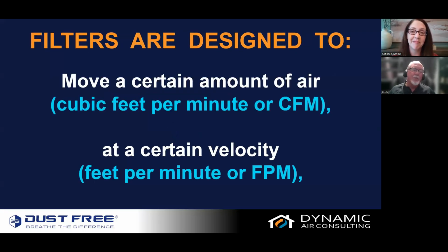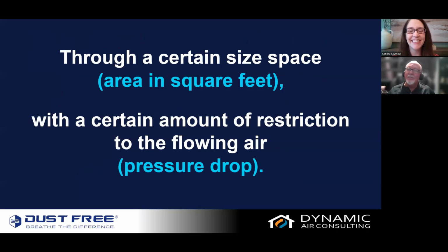So we're going to talk about how you can't just throw a filter in place without understanding the cause and effect. Filters are designed to move a certain amount of air, cubic feet per minute or CFM, at a certain velocity, which would be feet per minute or FPM. I tried to say those two in one. Through a certain size, or what we call net free area in square feet, with a certain amount of resistance to the flowing air through the filter. We call that pressure drop. So those are the four main measure points that we have to be concerned with when designing a filter into our system.